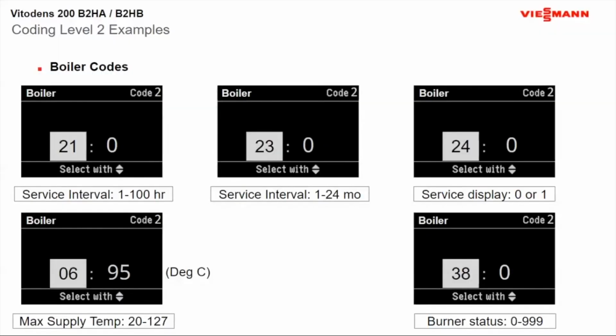If you did choose the boiler mode there, this is where boiler and coding level 2, remember how we had general, now boiler. So you go into coding level 2 and now click OK on boiler. This is where you can put your service intervals. You can do it in hours. You can do it in months. You can have it display a wrench or no wrench.